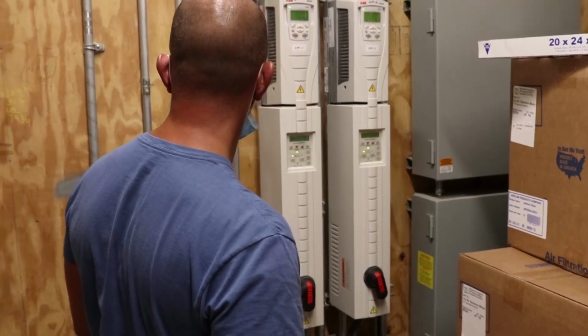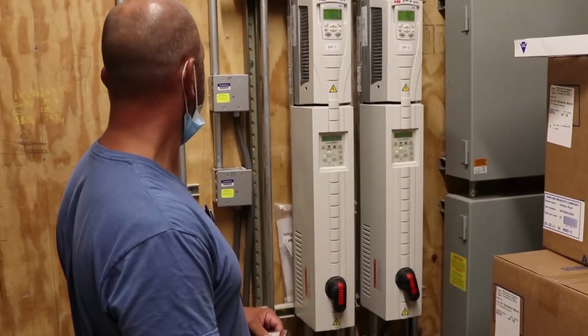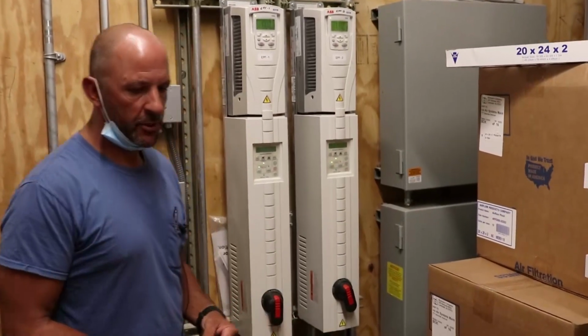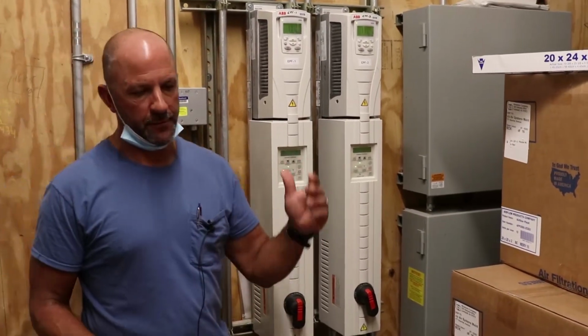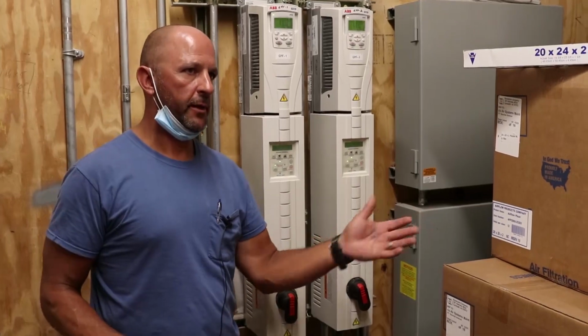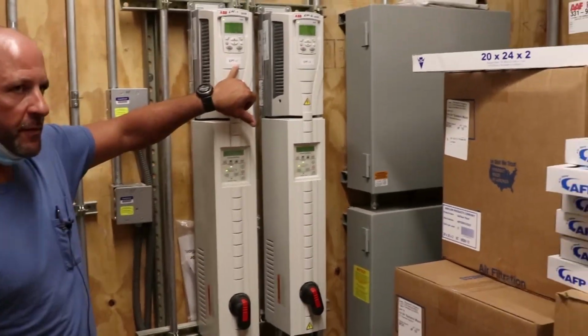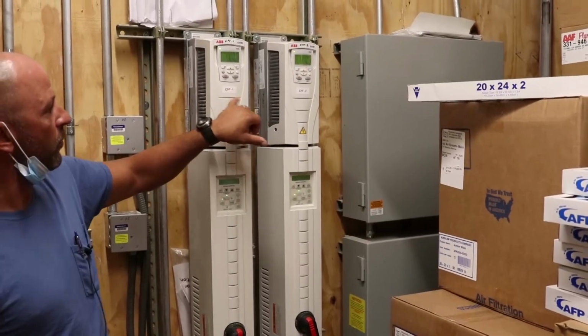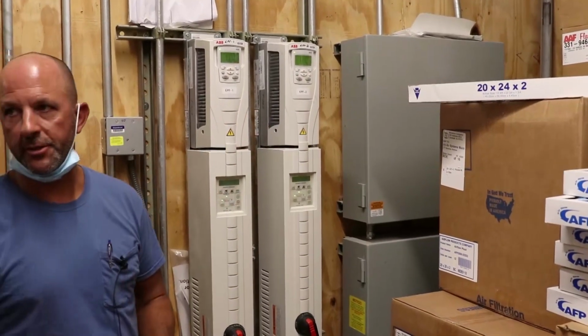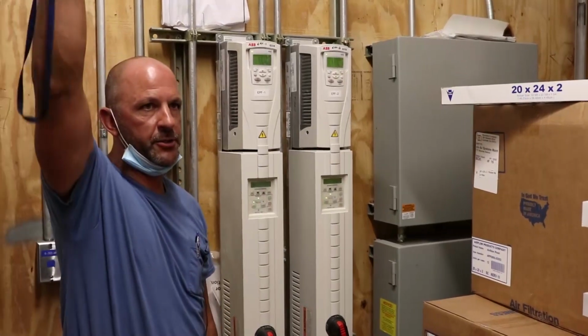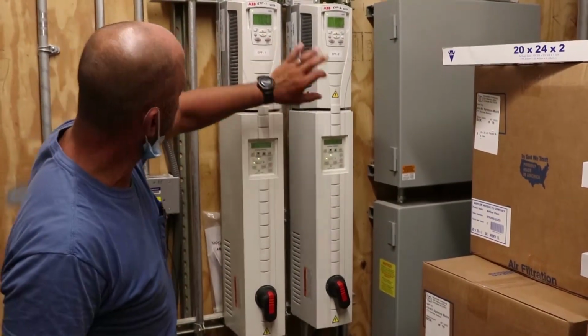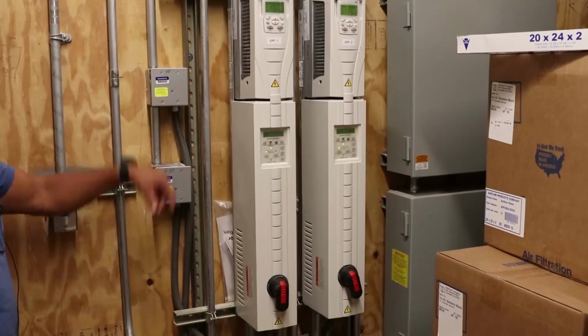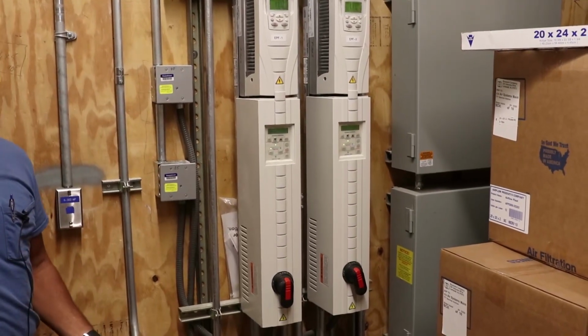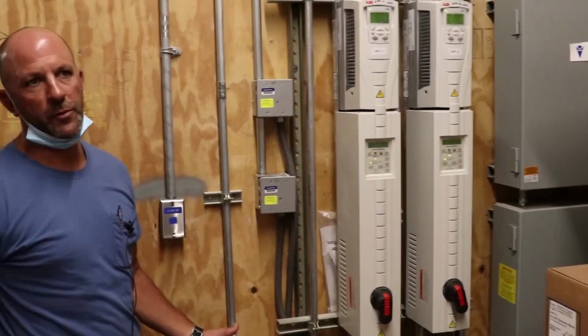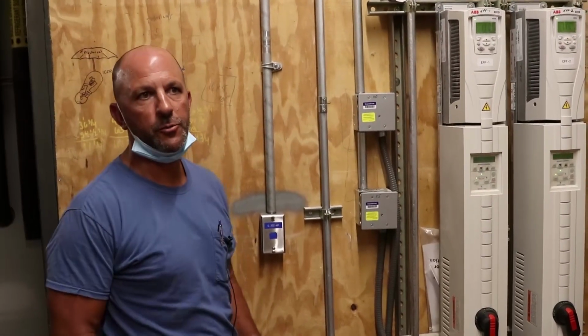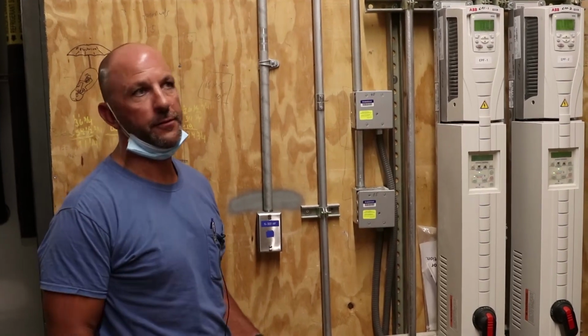All right. So we talked about all these fans being on drives. Most of the drives are in the 5th floor A electrical room or 5th floor B electrical room. These 2 elevator pressurization fans, that's what the acronym EPF stands for, 1 and 2. 1 being the bigger one that pressurizes the shaft, 2 being the smaller one that pressurizes the room. You leave these in auto, and on a fire condition they send a signal and start the drive. That's it. They pressurize the room, they pressurize the shaft, and it keeps smoke out of the room and out of the shaft.